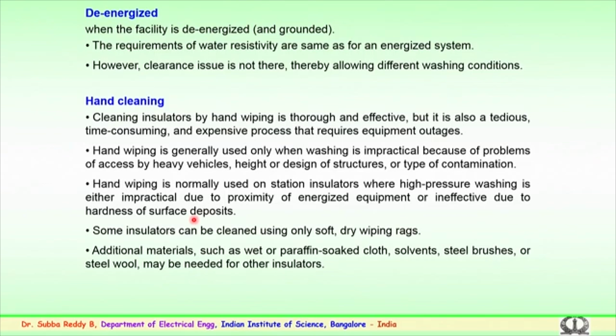Particularly the steel brushes or steel wool, which may be needed for some of the insulators, cannot be used for the polymer insulator, which is soft. So, care has to be taken, as this depends on the surface conditions, the material to be removed, and the hardness of the material deposited on the surface. Such materials are used to clean the insulation, bushings, or substation equipment where these insulators are housed.